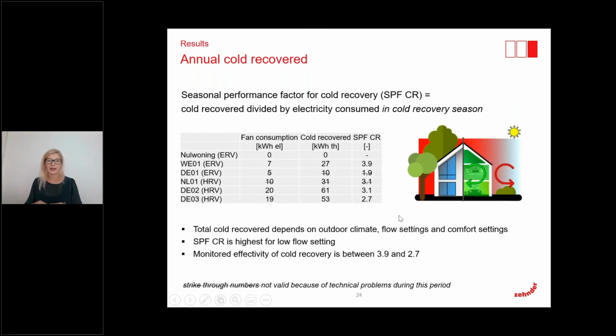Now let's move to annual cold recovered. Here, the main principles are similar to those for heat recovered. Then we have the seasonal performance factor for cold recovered. In the same way, the cold that we have recovered is divided by the electricity consumption in the cold recovery season. So we cannot take these values when we have to heat, or vice versa. For heat recovery, we will not consider cooling, because it is not reasonable to do one or the other in different season times.